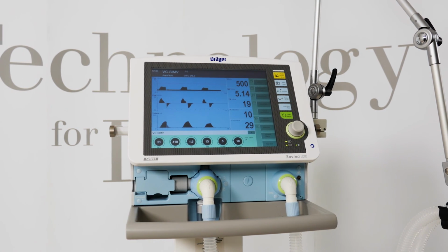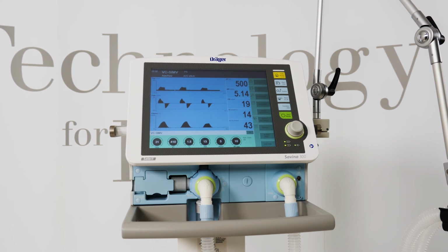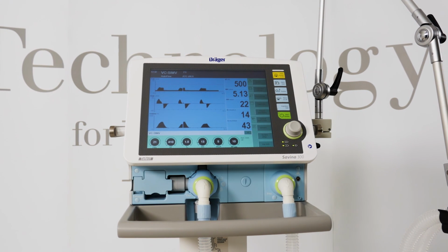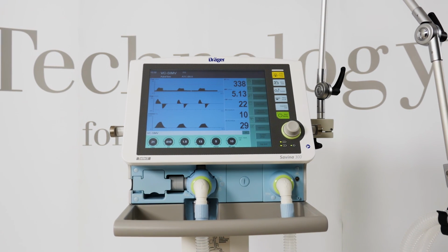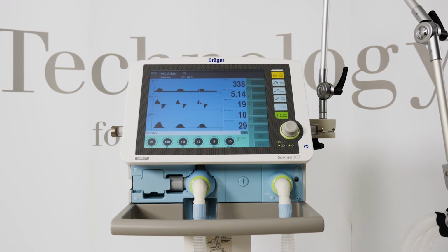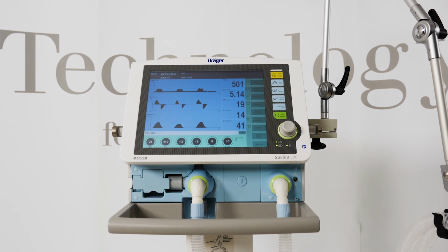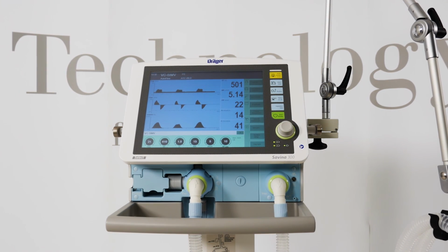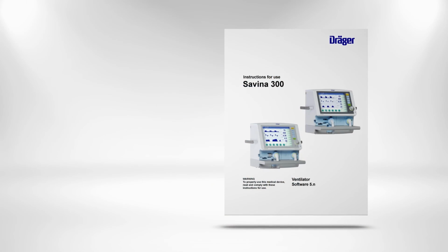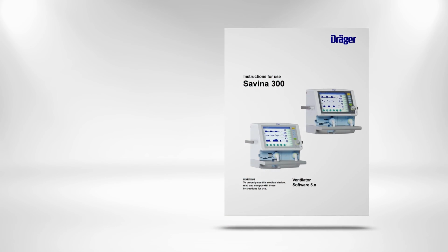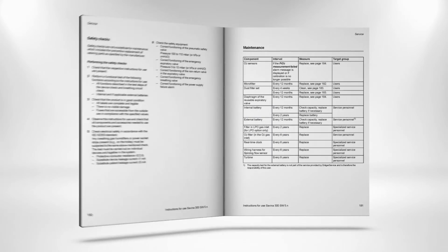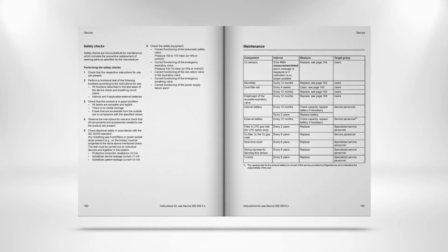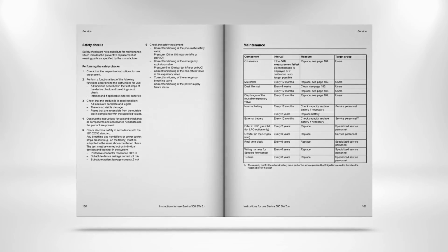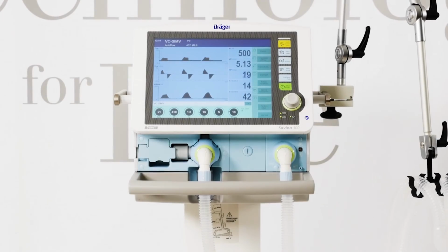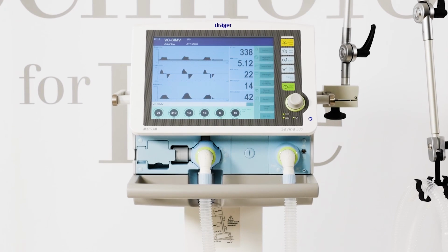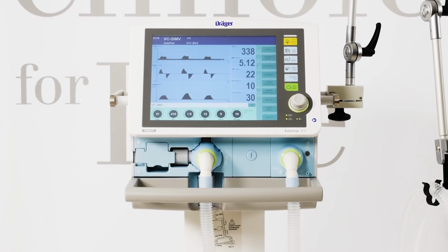You should thoroughly inspect all items for damage and wear, for example cracking, embrittlement or pronounced hardening, and residual soiling. Device malfunctions are possible due to wear and material fatigue of the components. To maintain the proper operation of all components, this device must undergo inspection and preventive maintenance at specified intervals. Please find the preventive maintenance intervals in the maintenance table. After completing all steps, Savina 300 Select is ready to be used on the next patient.